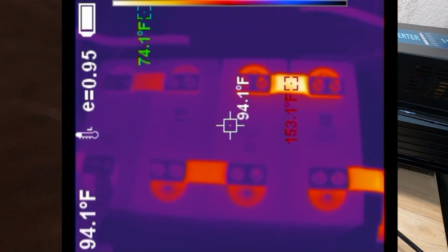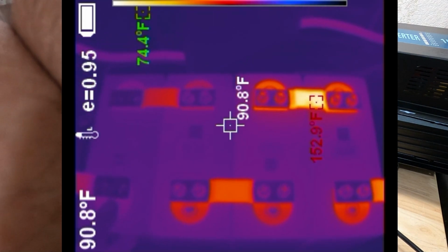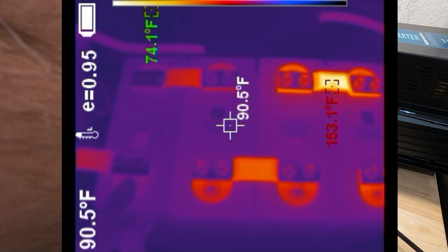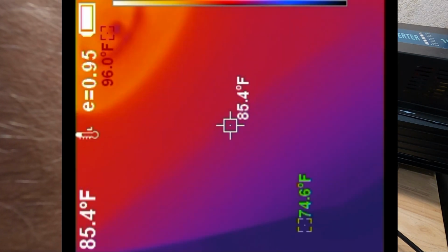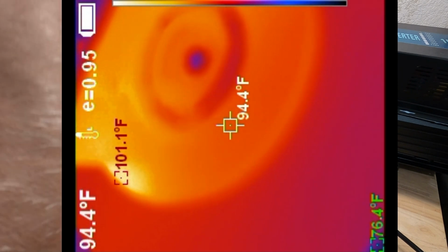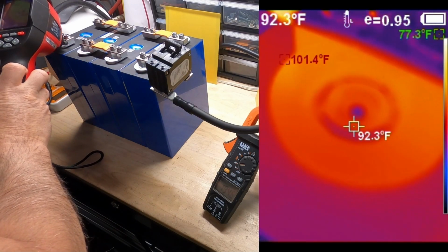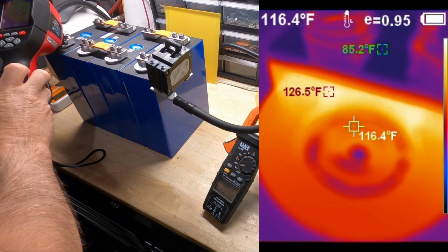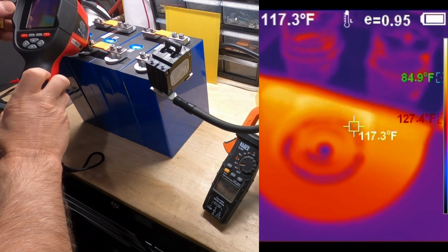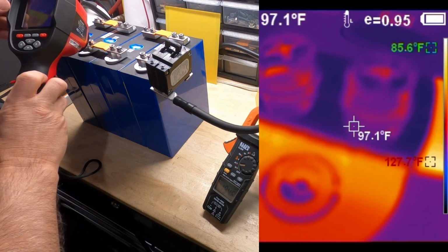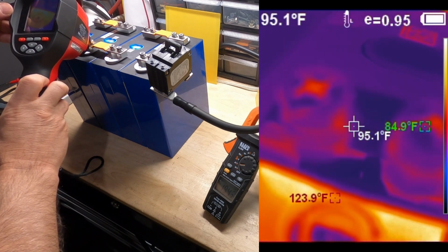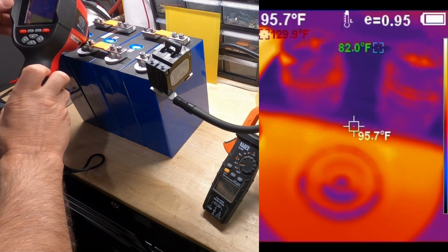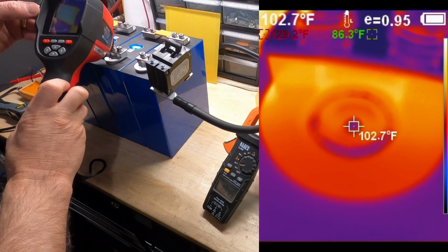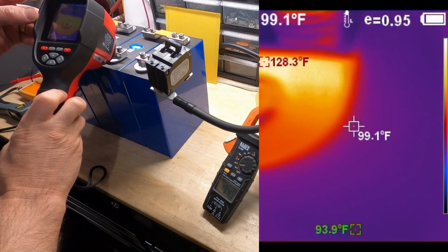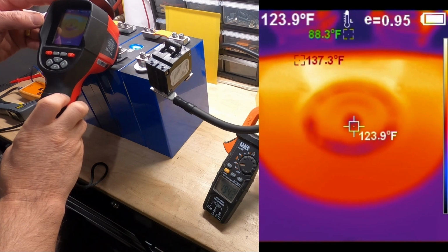So now, you can see that stud over here, cell number 4, is running the coolest, actually. It's cooler than all the others. Check it out, you can't even see it on the heat profile. Look at that, beautiful. 101 degrees. We'll go over here. Look at that. 130 degrees. That's interesting because the actual head of the bolt is not very hot. So I think it's just creating a lot of resistance, and the heat's being generated right on the terminal stud of the cell. That's crazy.